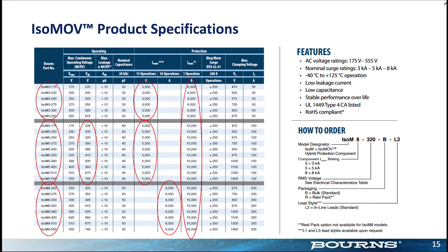I don't know if you can see it, but I moved the slides to the datasheet numbers, and those voltages dropped down to 200-something volts DC. The question was, will it clamp down to 400 volts? And the answer is yes. Well, it depends on the operating voltage too. Right, exactly. It's got to be above your operating voltage, and then you get whatever the clamping voltage is. And that's what's hard, right? You want the operating voltage high and the clamping voltage low, and the closer those two get, the harder and harder it is to make devices.